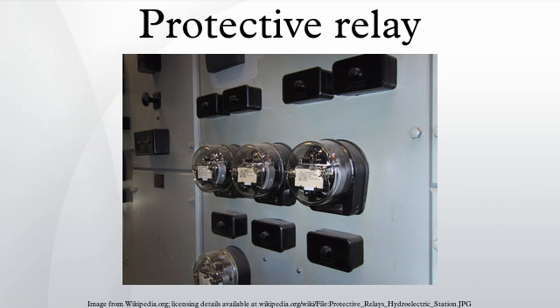Digital. The functions of electromechanical protection systems are now being replaced by microprocessor-based digital protective relays, sometimes called numeric relays. These convert voltage and currents to digital form and process the resulting measurements using a microprocessor. The digital relay can emulate functions of many discrete electromechanical relays in one device, simplifying protection design and maintenance. Each digital relay can run self-test routines to confirm its readiness and alarm if a fault is detected. Numeric relays can also provide functions such as communications interface, monitoring of contact inputs, metering, waveform analysis, and other useful features.